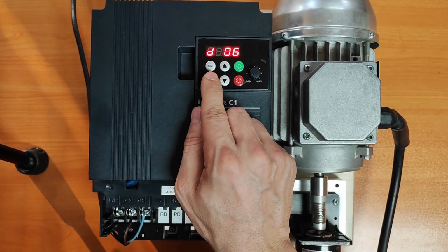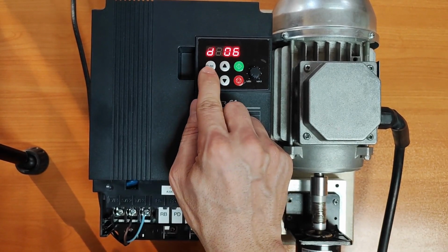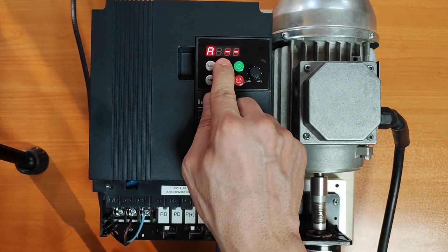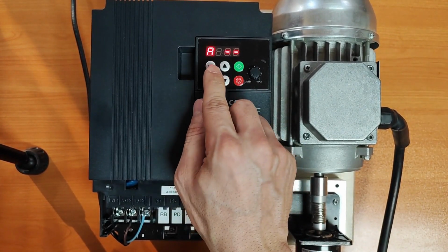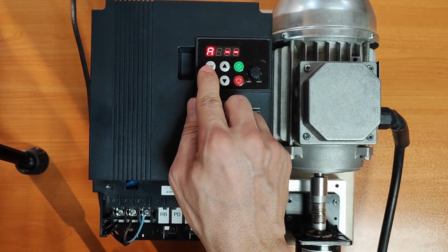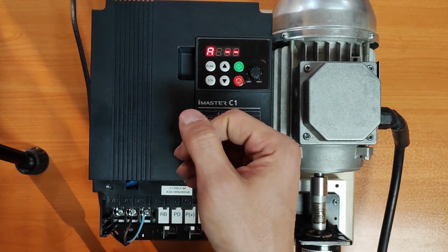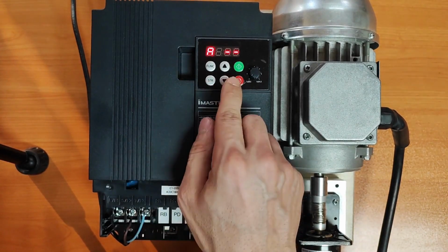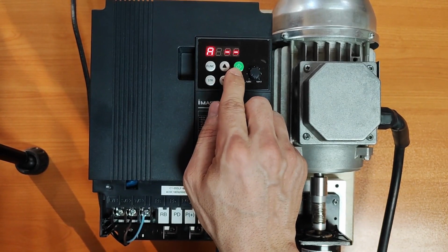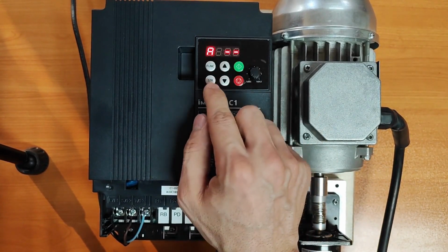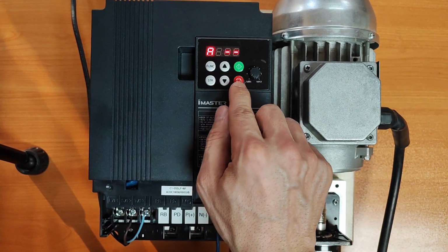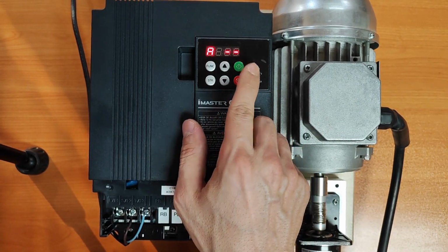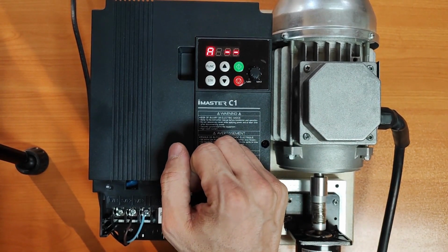So it's the function key to go to parameter groups, the up and down keys to move between parameter groups, and the function key to enter a parameter within a parameter group. And to save the value that we've set, we use the STR key. The green key is for starting the inverter when we want to do it from the keypad, and the red key is for stopping the inverter from the keypad. A knob is also provided here, which can adjust the inverter's output frequency.